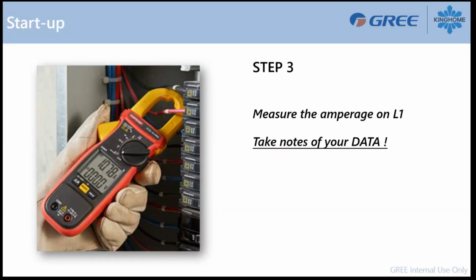This is what we are looking for when we have an air handler running at full capacity with the duct heater active. For example, if we have a 2-ton system with a 5 kilowatt heater in it, I'm about to see around 24 amp-ish. It really depends on the static pressure and on how the system is installed, but around 24 for this kind of installation, a 2-ton with a 5 kilowatt.